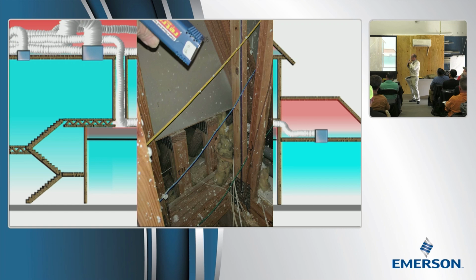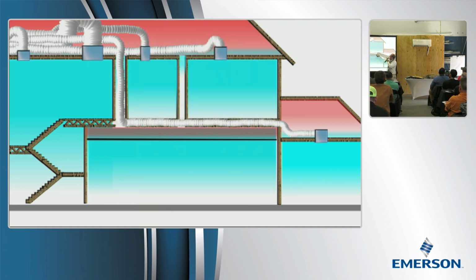Now, the harder thing to be successful at is sealing in the ends of these floor joists. What you're looking at here is the ends of the joists running through the floor. So in that case, you've got 120 grain moist climate zone 1 air around your duct, but you've only got 70-degree rooms around it. So you've got all the moisture, but you don't have any heat because it's sheltered by the room above.